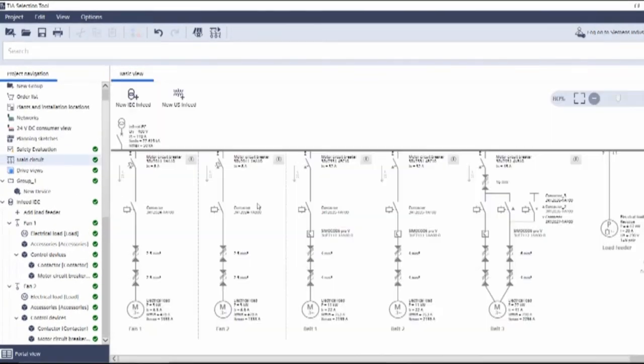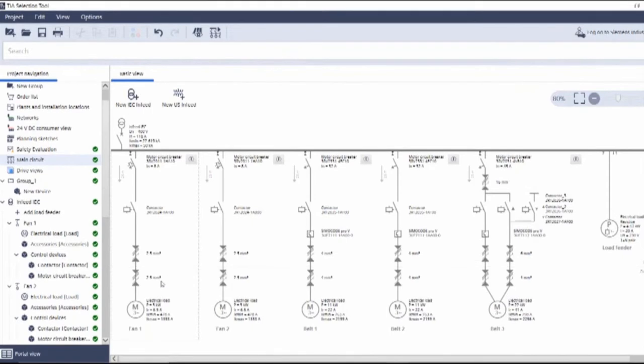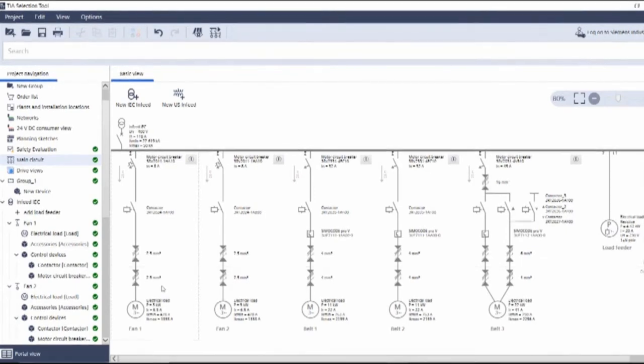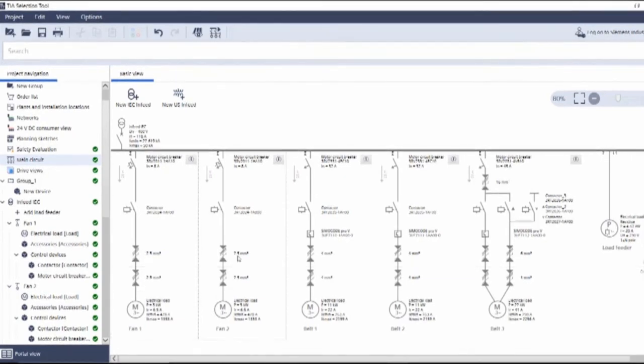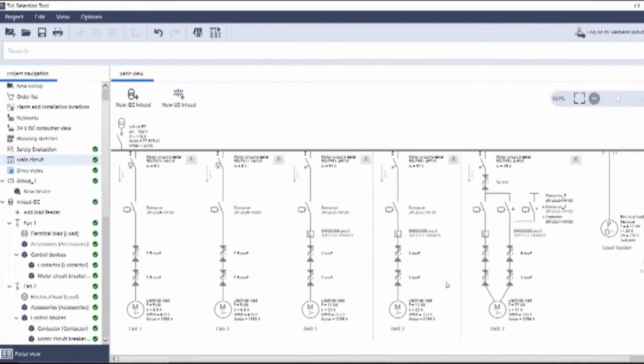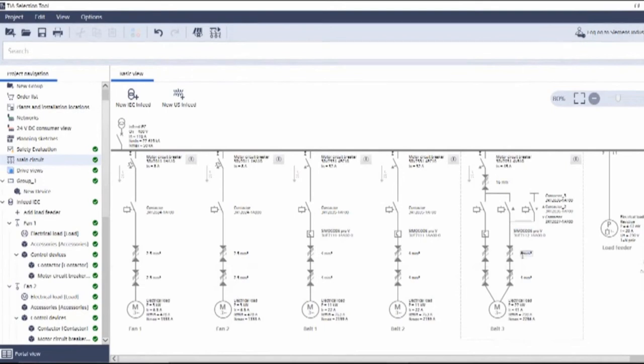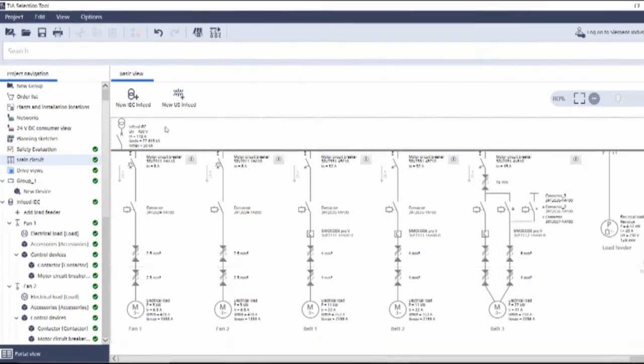Let's go back to our main circuit. What else have we got? So we've taken into consideration all of the cables, i.e., for example, how many loaded cables are there on the tray? What are the correction factors? The tool does all this for you. So now you can see we've got cable size here on the small motors, two and a half mil. Then we've got four mil here. And we can see on the Star Delta, which is a bit heavier, we've got the cable sizes done for us.